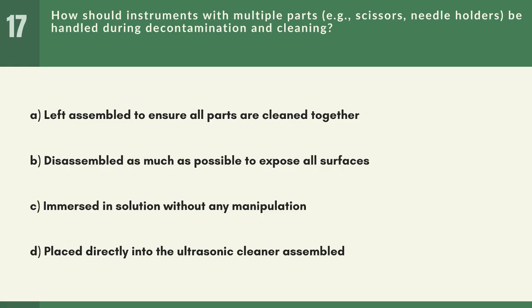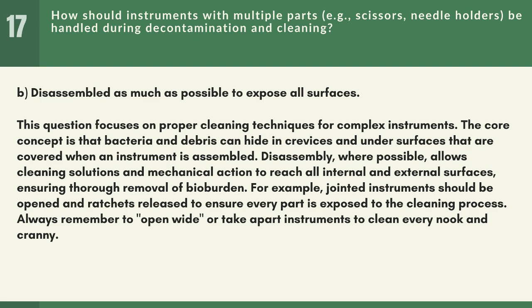Question 17. How should instruments with multiple parts, e.g., scissors, needle holders, be handled during decontamination and cleaning? A. Left assembled to ensure all parts are cleaned together. B. Disassembled as much as possible to expose all surfaces. C. Immersed in solution without any manipulation. D. Placed directly into the ultrasonic cleaner assembled. Answer: B. Disassembled as much as possible to expose all surfaces.